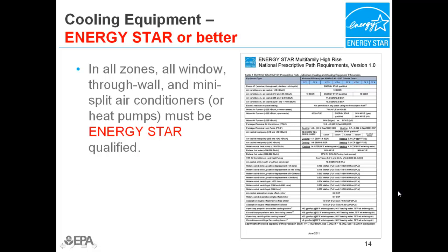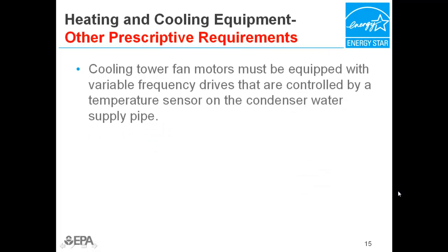In all zones, all room air conditioners and mini splits must be Energy Star qualified. To wrap up the heating and cooling equipment requirements of the prescriptive path, if central cooling is provided using a cooling tower, the cooling tower fan motors must be equipped with variable frequency drives that are controlled by a temperature sensor on the condenser water supply pipe. For systems not mentioned in this webinar, please review Table 1 of the prescriptive path.